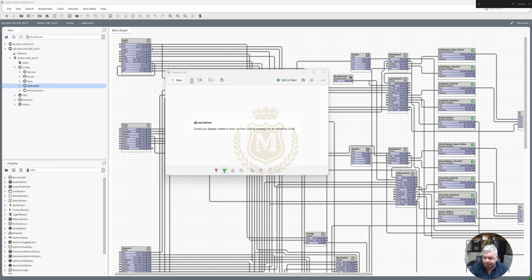Now the temperature sensor is really not the way to go. You want a wet bulb sensor really for monitoring the internal temperature that's coming back on the AHU from the area, and you also want that same sensor or another sensor type, exactly the same, a wet bulb sensor for the outside air. Free cooling in AHUs is a smart and sustainable method that optimizes the natural outside air to maintain indoor thermal comfort. It requires precise control and monitoring of the air properties to be effective.